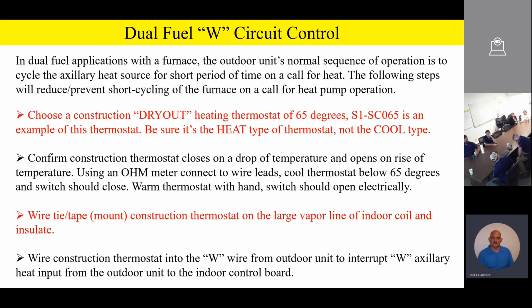Every time the outdoor unit sees a demand for heating, it's going to output 24 volts on that W signal, and it's going to bring the furnace on for a short period of time, typically for about 1 minute. Well, that's not a really good thing with a furnace, because we don't want to sit here and short cycle the furnace. So what we're going to do is add something brand new, by the way, in our program.